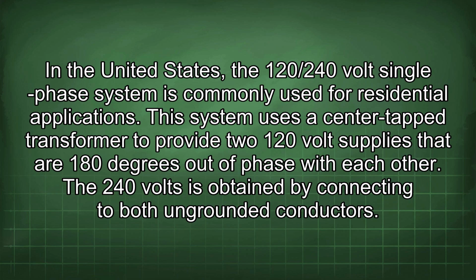In the United States, the 120/240 volt single-phase system is commonly used for residential applications. This system uses a center-tap transformer to provide two 120-volt supplies that are 180 degrees out of phase with each other. The 240 volts is obtained by connecting to both ungrounded conductors.